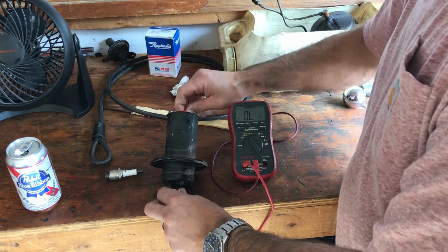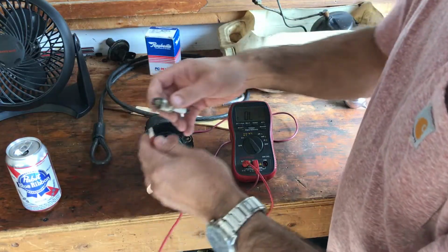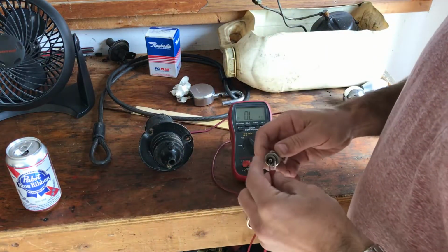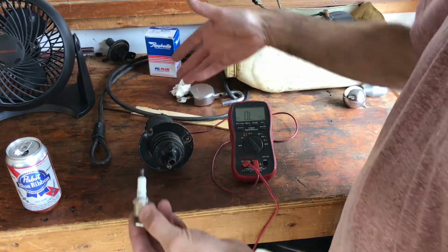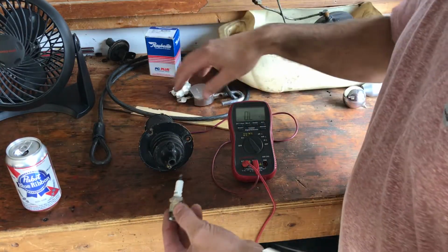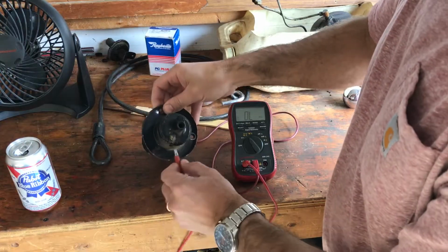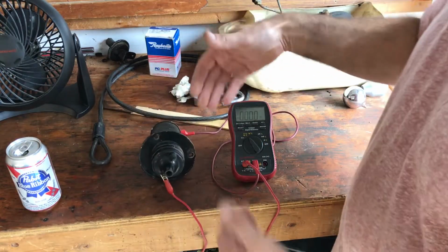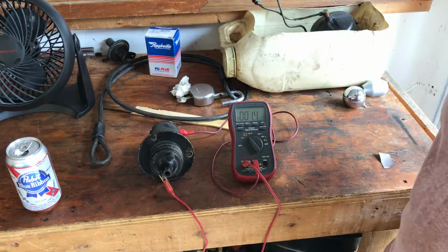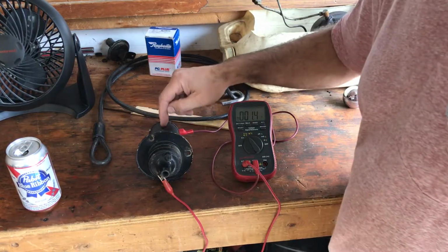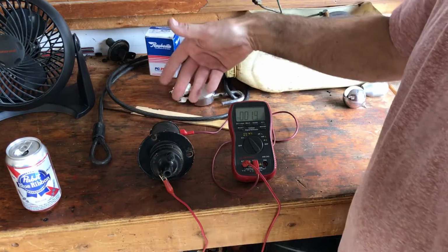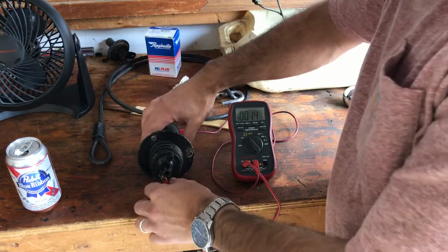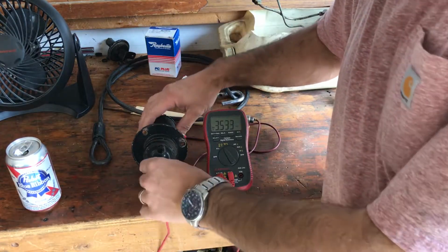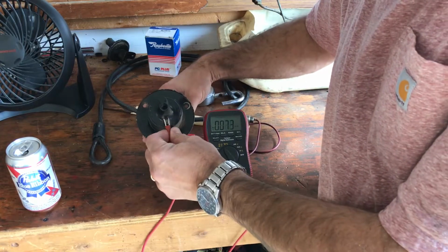I wonder if we could measure this. If you put your multimeter across here, you'd get infinity, zero ohms, because there's no connection, no ohms, can't make a circuit. So if you hook up your multimeter to measure resistance on a coil and get infinity, it tells you there's a broken wire in the coil, it can't make the circuit, so your primary coil has failed. If you're troubleshooting your coil, you can use that for reference.